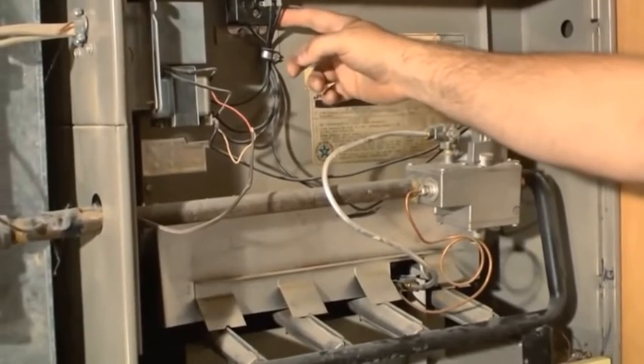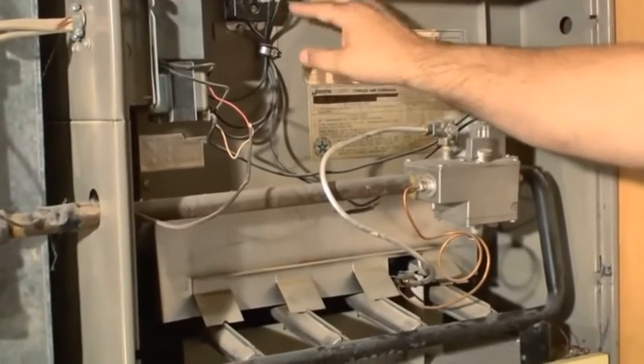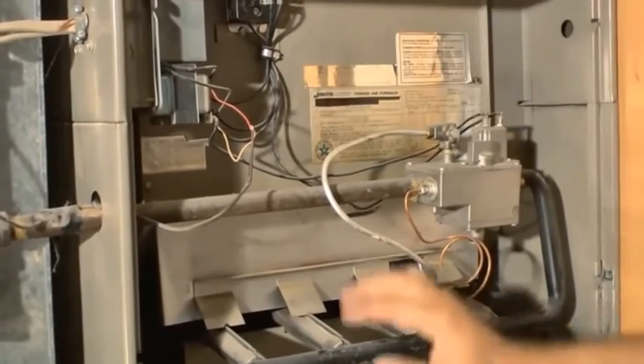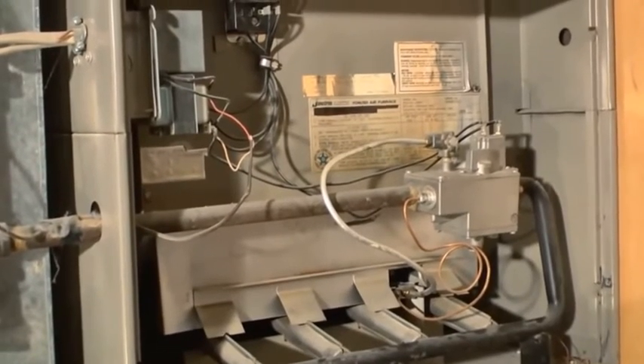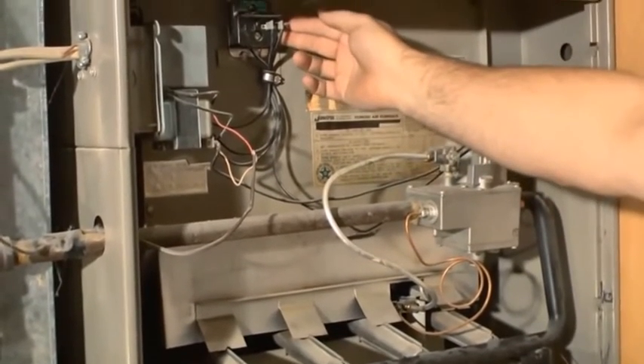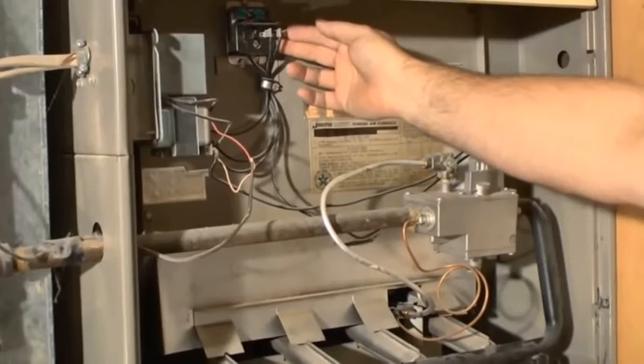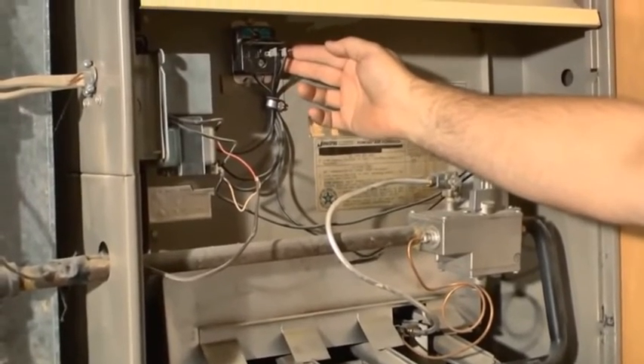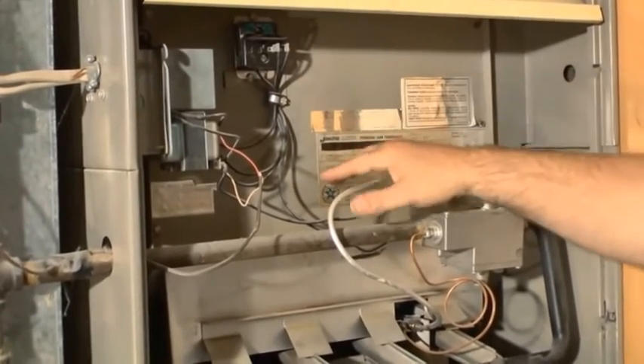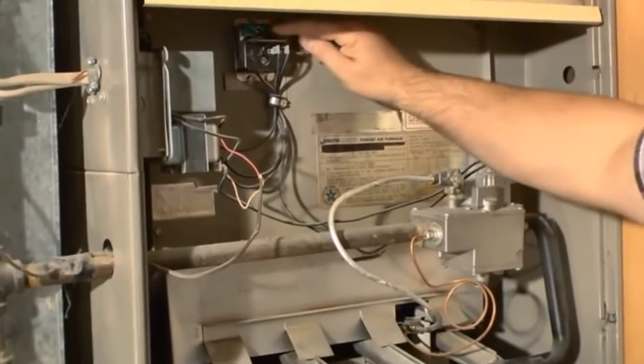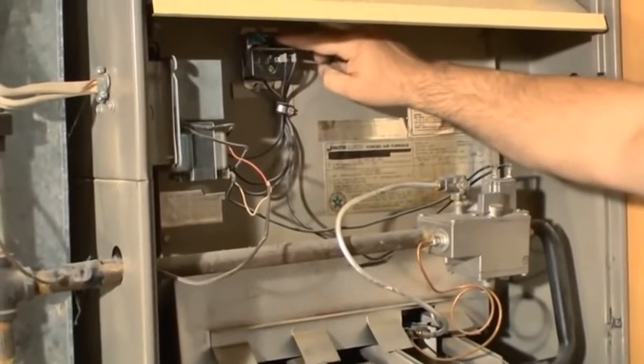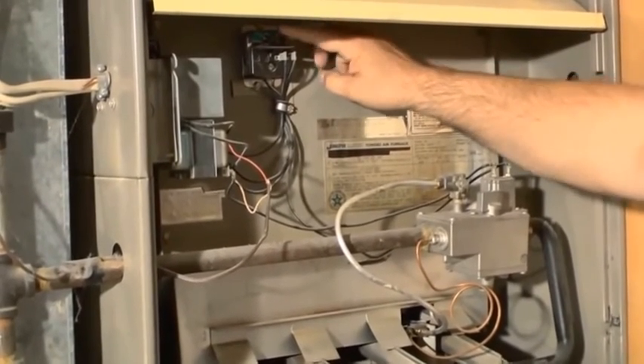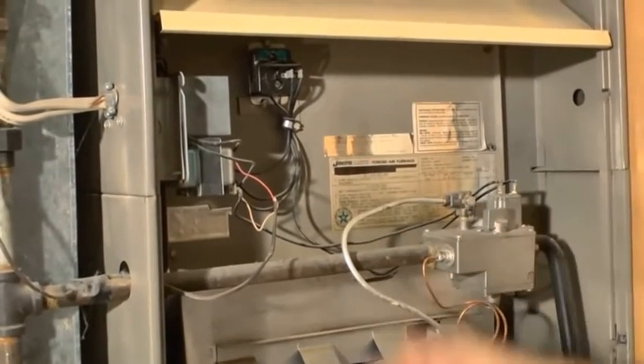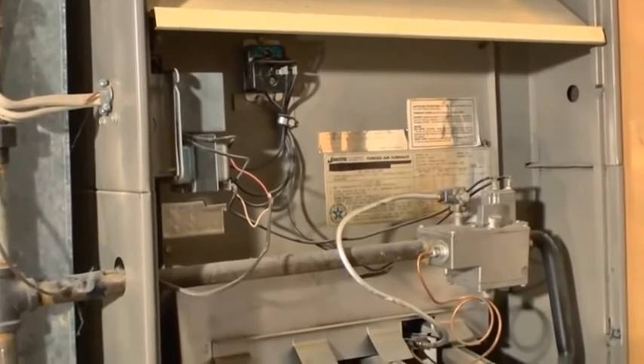It also has the ability, when the temperature gets to a certain amount, to turn the fan on in this furnace. And after there's been a call for heat, it turns the fan off when the temperature of the air gets down to a certain temperature. That's adjustable in here, and it's set at 95 degrees right now. So that's actually a good setting. We recommend 85 to 95.